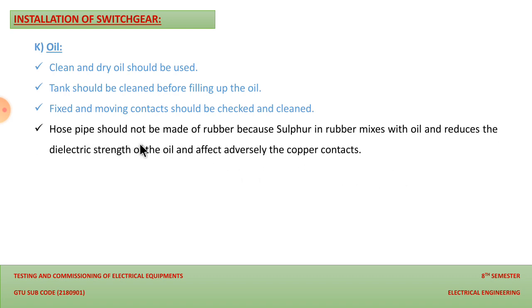And the hose pipe should not be made of rubber, because the sulfur in the rubber mixes with the oil, which reduces the dielectric strength of the oil. So when the sulfur mixes with the oil, the dielectric strength of the oil will reduce. As obvious, we are using oil for insulation purposes and for cooling purposes inside the switch gear. So we have to check the quality of the oil, and we need to check according to the future operations also. So yes, the hose pipe should not be made of rubber, because sulfur in rubber mixes with the oil and reduces the dielectric strength of the oil, which adversely affects the copper contacts. Those are the points we should keep in mind while we are installing our switch gear.